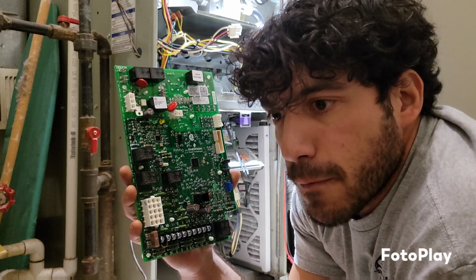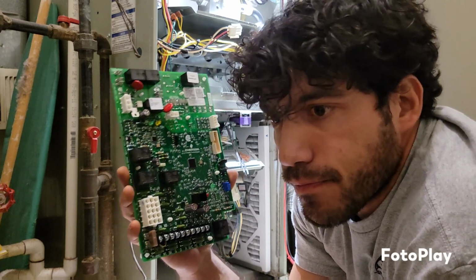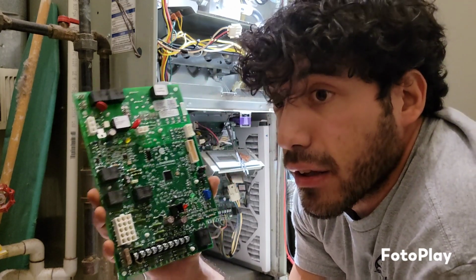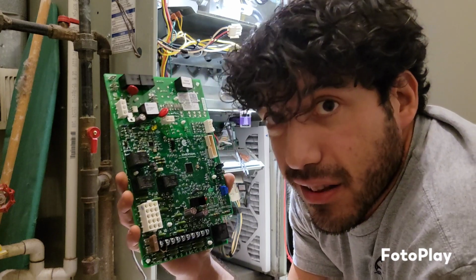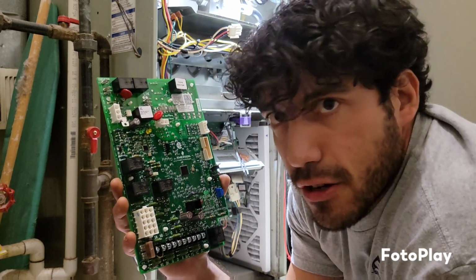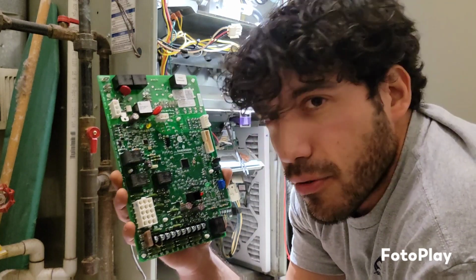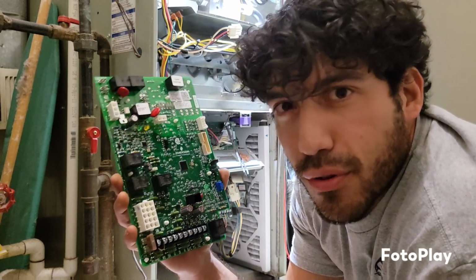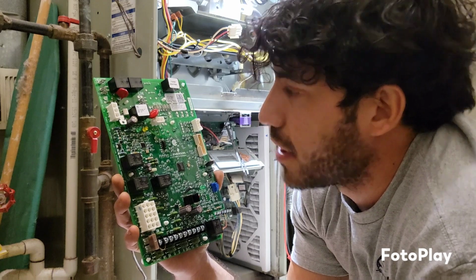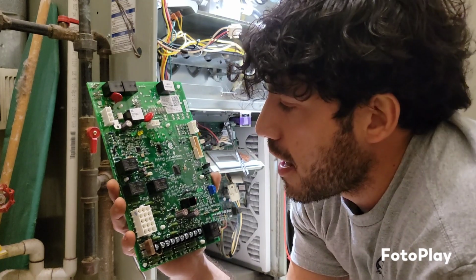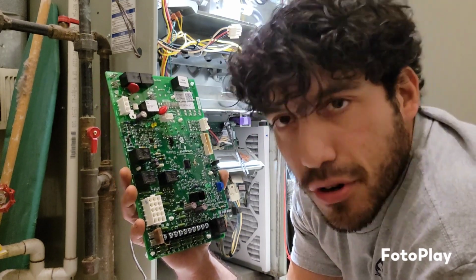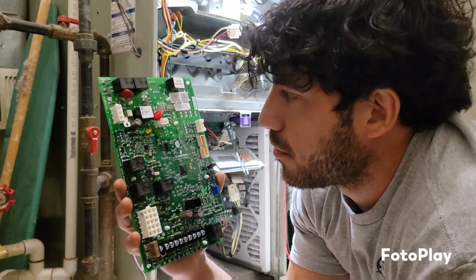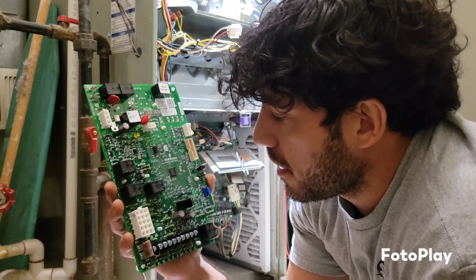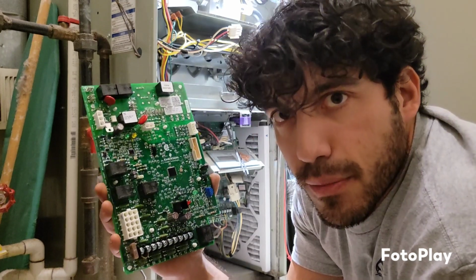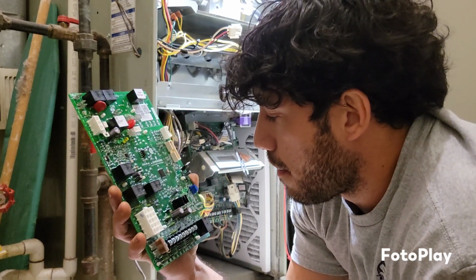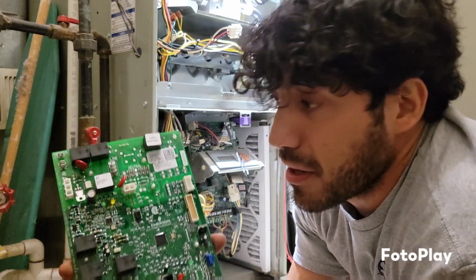So instead of it being a unit where it'll cycle at like 40% or 100% capacity depending on demand, right? It just goes 100% all the time. So again, what's the point of having a high efficiency unit if you're going to do that, right? But unfortunately, they don't have the extra wire that they need, and they don't have the proper thermostat for that. So again, we're just going to jump it out. It's going to come on at 100% capacity, but it does take away a little bit from the efficiency of the unit. But at least we'll get them heat, right?